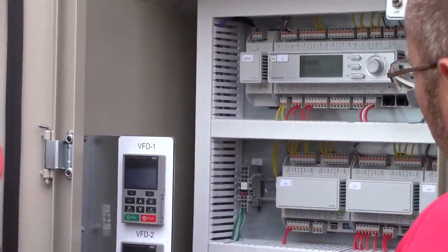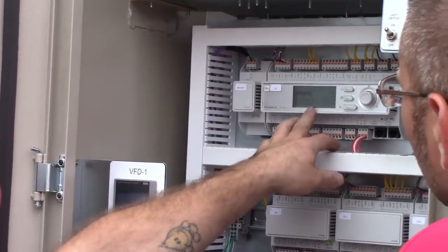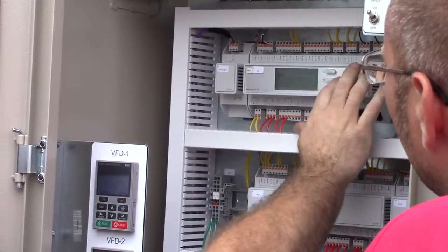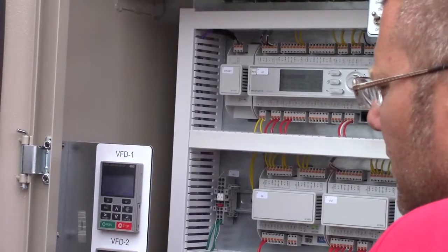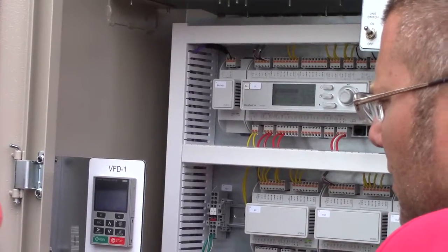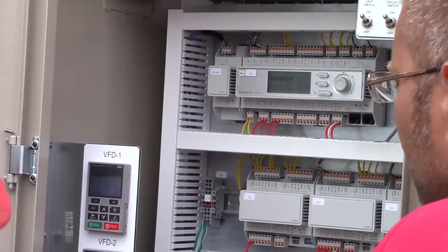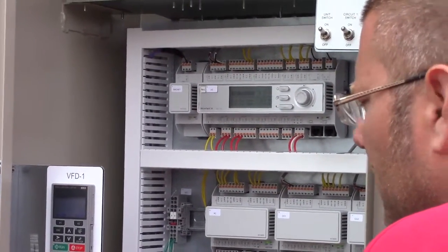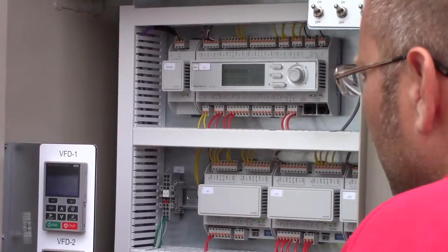And expansion valve. You can see how it's controlling the superheat, what its targets are, and then in your data menu, superheat. The target changes based on operation, so it's a fully variable target because they're electronic. We can do that. Years ago, it would be 6 to 8 or 8 to 10, depending on the chiller application. We didn't vary much.